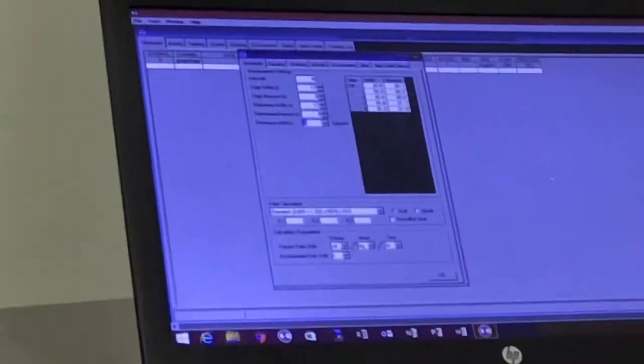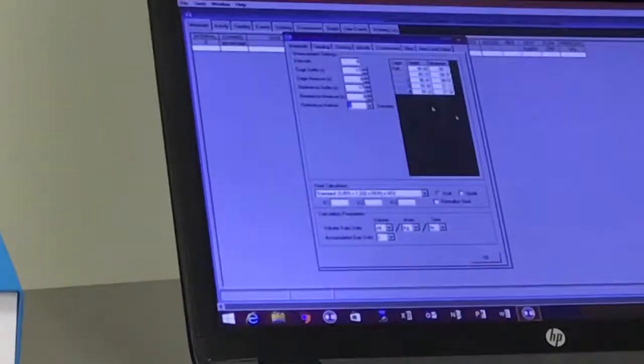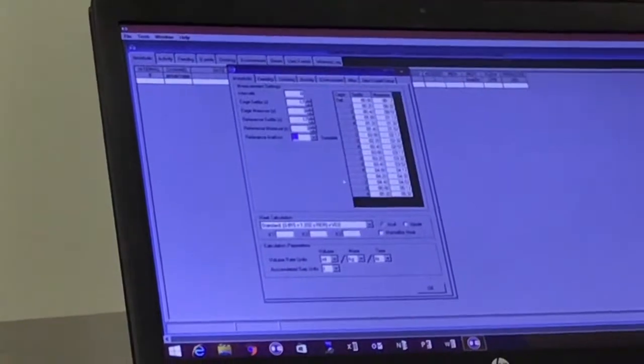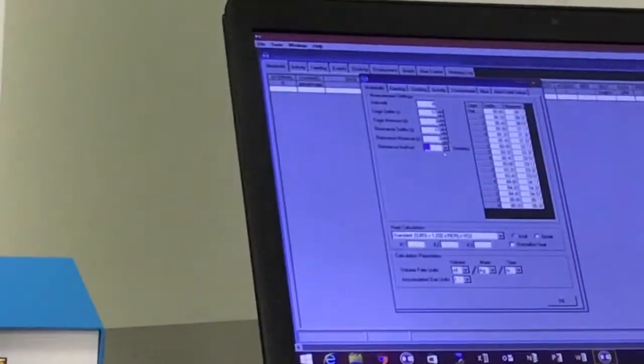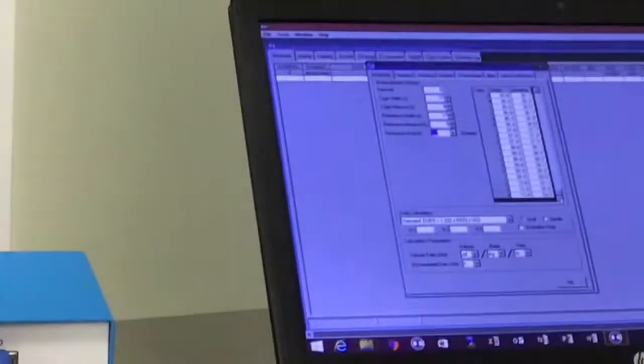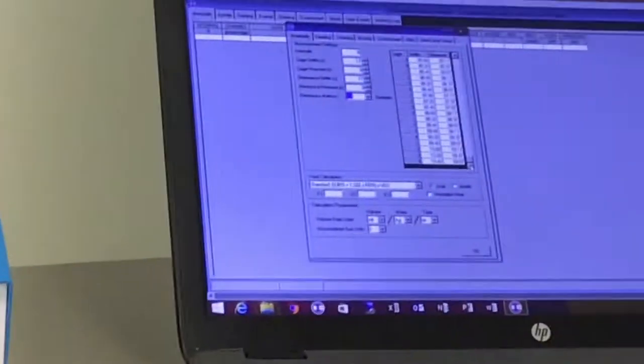Me, I run the same experiment, and I'm about to start it, lock this door and go home and come back the next day. I will probably do 16, where I do 4 cycles of 4 cages, 16 samples, and reference 1. Or even on a weekend where no one is going to come and there's no janitor coming in and I want a whole bunch of data, because a reference takes the same time as a sample. 17-second purge, the last sample line, and 3-second reading room air.